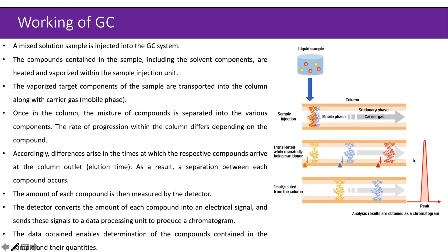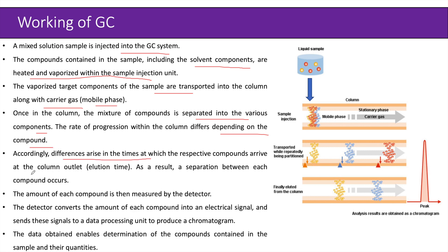Let us see the working of gas chromatography. A mixed solution sample is injected into the GC system into the solvent stream. The compounds contained in the sample including the solvent components are heated and vaporized within the sample injection unit. The vaporized target components are transported into the column along with the carrier gas, our mobile phase. Once in the column, the mixture of compounds is separated into various components. The rate of progression within the column differs depending upon the compound, and accordingly differences arise in the elution times at which respective compounds arrive at the column outlet, resulting in separation.